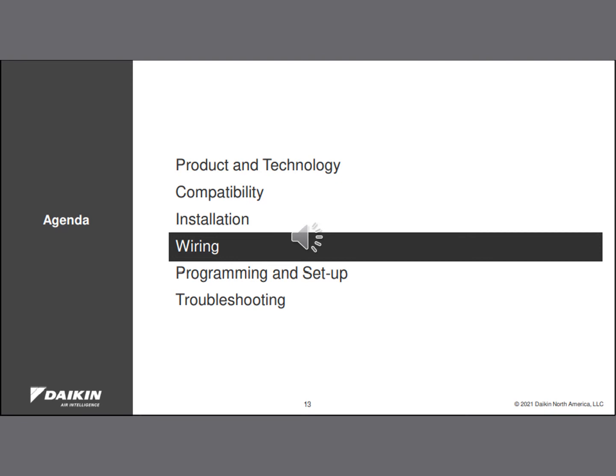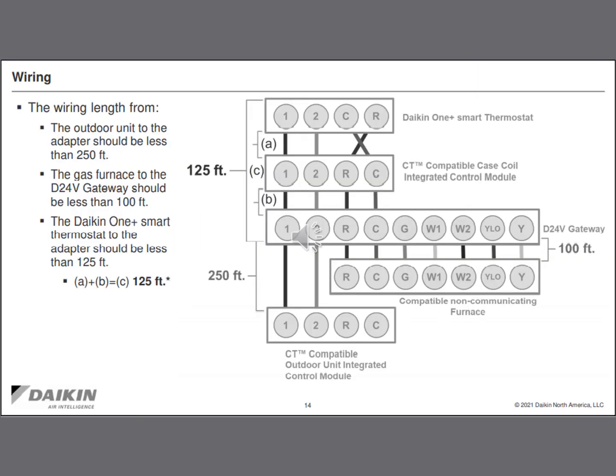Okay, so let's talk a little bit about wiring. The wiring for the D24V Gateway is very similar to a normal Daikin FIT AC system. As you can see, we wire from the Daikin 1 Plus Smart Thermostat down to our EEV coil, and then from the coil, instead of going directly to a communicating furnace with 1, 2, R, and C, we're going to take 1, 2, R, and C down to the D24V Gateway.